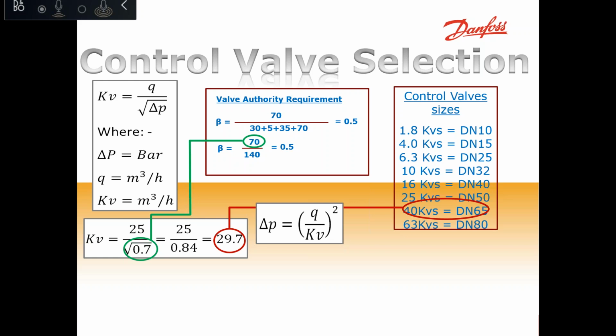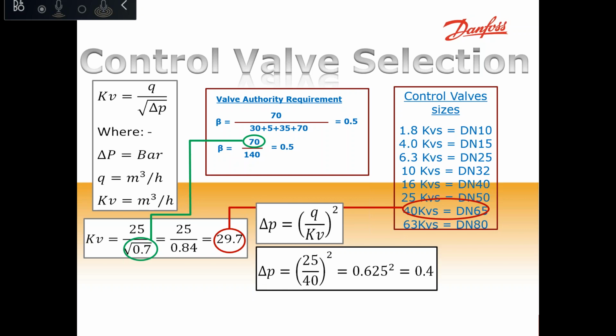Now, this step, which will make the system even worse, is what will be the pressure drop at the selected valve kV. And in our case, it's 25 divided by 40 squared, and it is equal to 0.4 bar, which was initially or originally selected at 0.7. Now the authority of the two-way valve will drop from 0.5 to 0.28. And a 0.28 authority means that, let's say, if we take an example of a linear valve, a 0.3 authority means that you will be able to control from 100% open valve up to 70% open valve, which means the controllable range is only 30% of the valve controllability. Okay, so this is the meaning of the authority in physical, in real life.